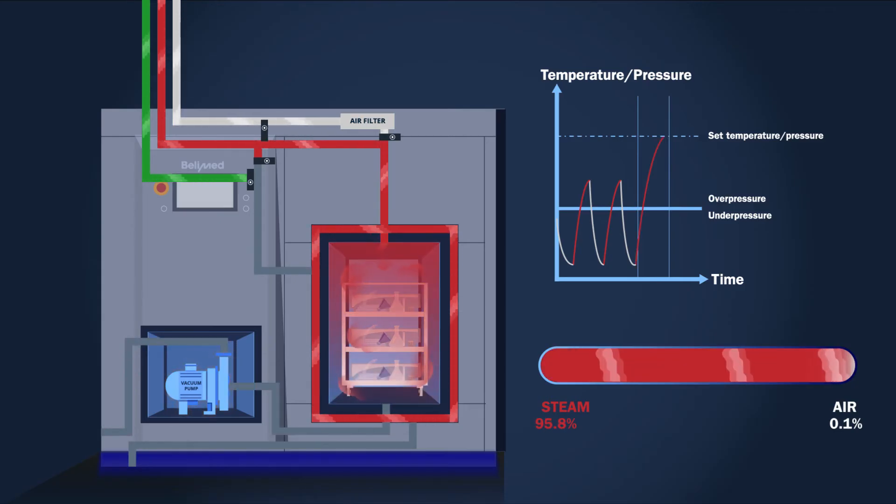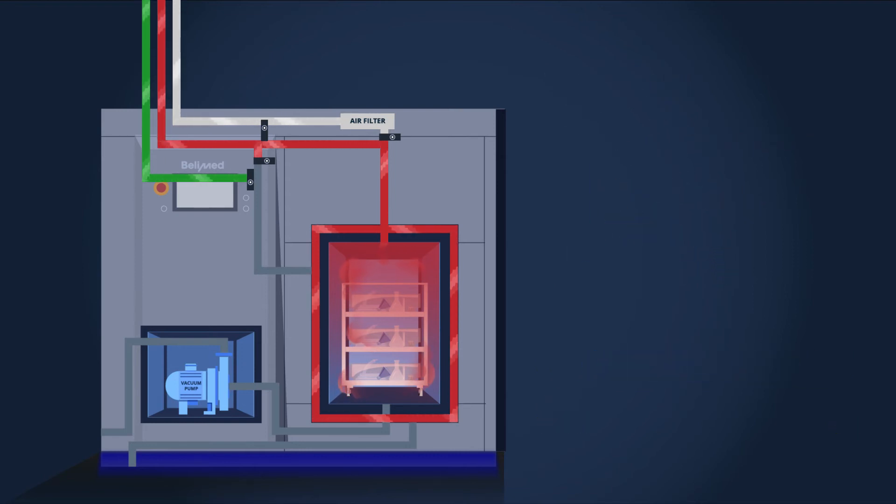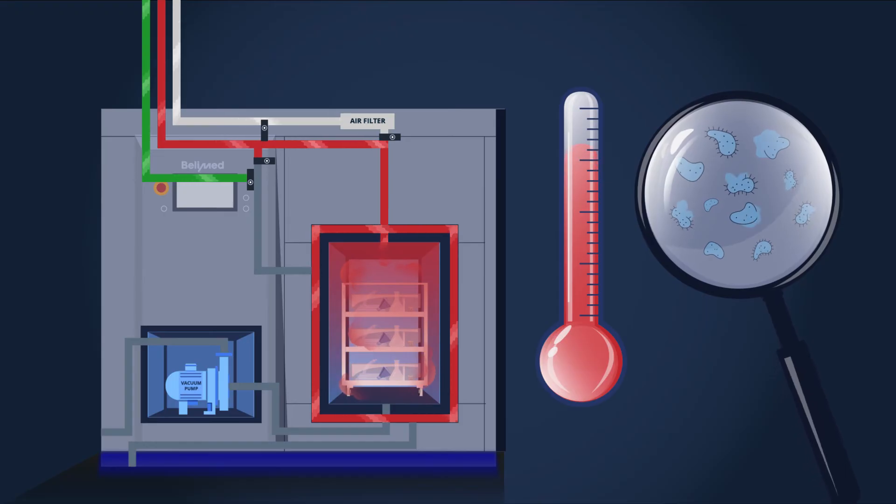Now the sterilization phase can start. The hot steam heats up all goods to the set sterilizing temperature. The heat kills all microorganisms. Depending on the products to be sterilized, the duration of this phase can be adapted.